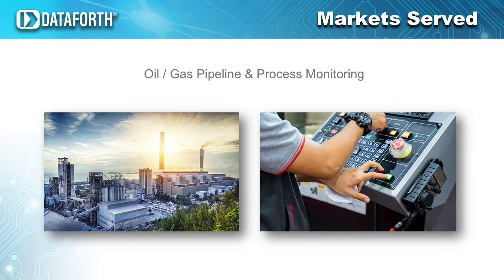Dataforth products can also be found in the field of oil and gas exploration. Rugged two-wire 4 to 20 milliamp transmitters connect remote field sensors to computers and control rooms to safely send and receive data between points A and B. Low-power communication links are especially useful in hazardous environments. Process monitoring applications such as food production, metal fabrication, or robotic process automation also benefit from high isolation and product durability.